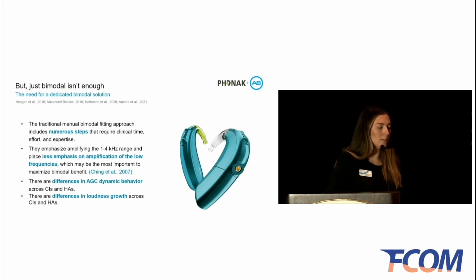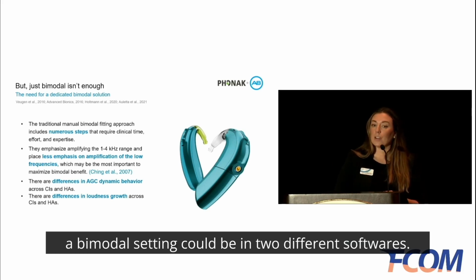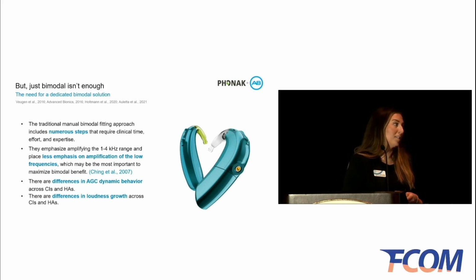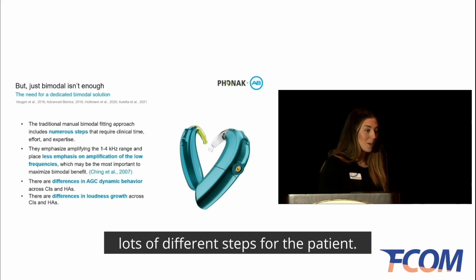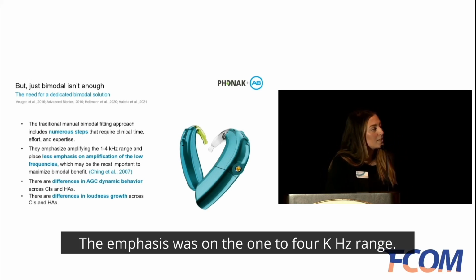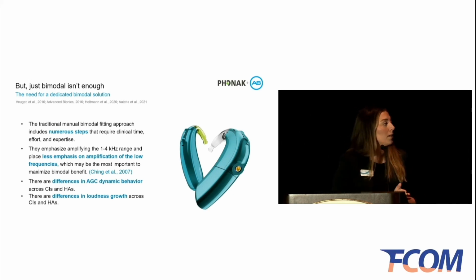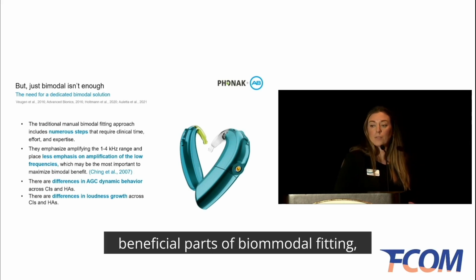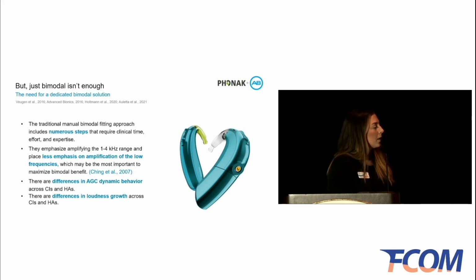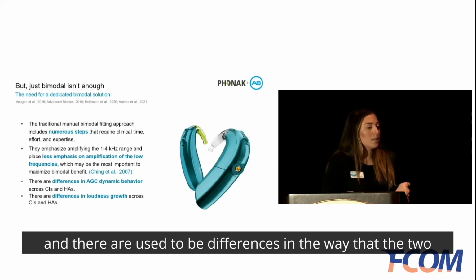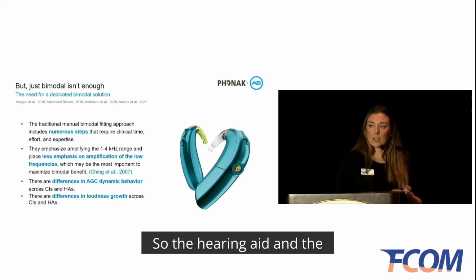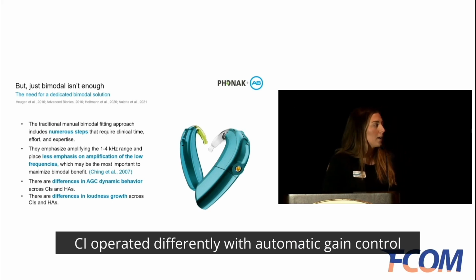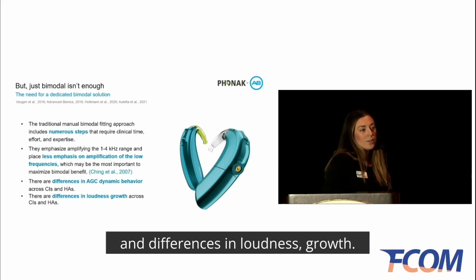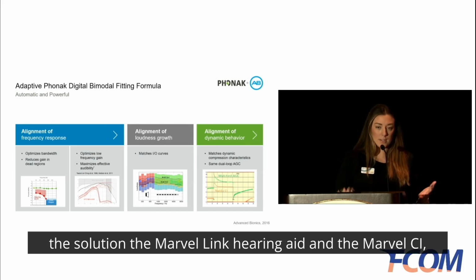So in the past, we know that a bimodal fitting could be in 2 different softwares. It may take the audiologist a long time with lots of different steps for the patient. The emphasis was on the 1 to 4 kHz range, but now we know that amplifying the low frequencies is really one of the most beneficial parts of bimodal fitting. And there used to be differences in the way that the 2 devices behave together. So the hearing aid and the CI operated differently with automatic gain control and differences in loudness growth. So Phonak and AB introduced the solution, the Marvel Link hearing aid and the Marvel CI.